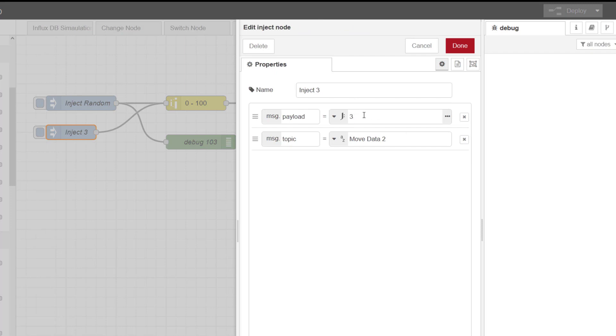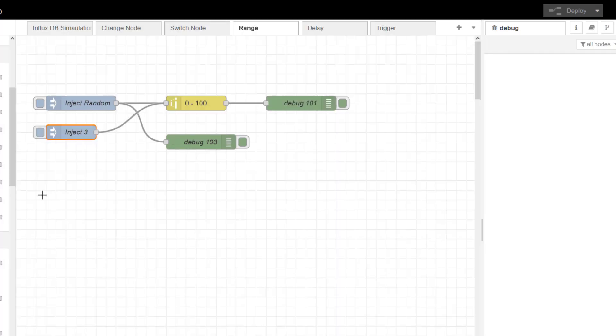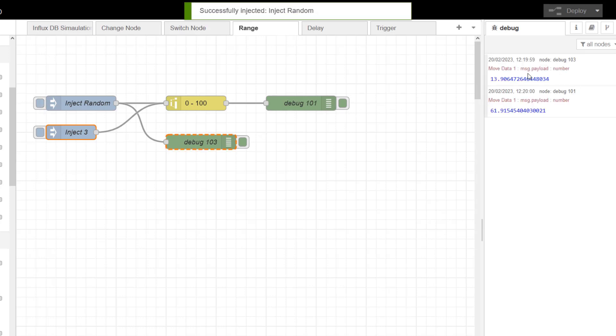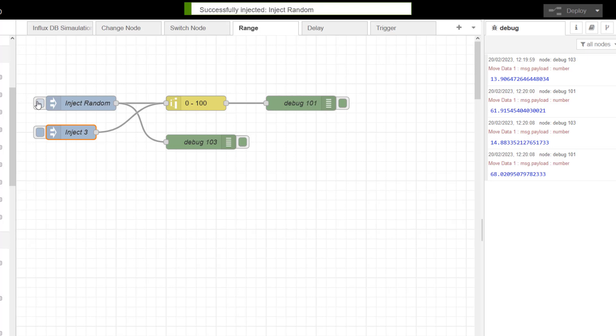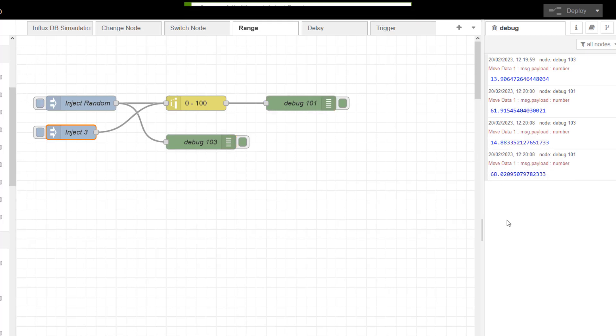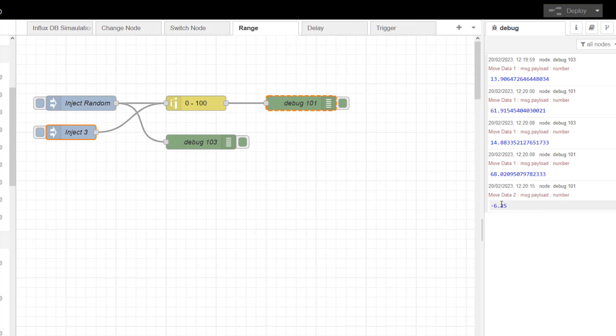So you can see what's happening. If I inject my random, I can see here that my milliamps coming in is 13 and I have an output of 61, and 14, 68. That's fine, I'm happy with that. But if I put in 3, which is less than 4, I now get minus 6.25.